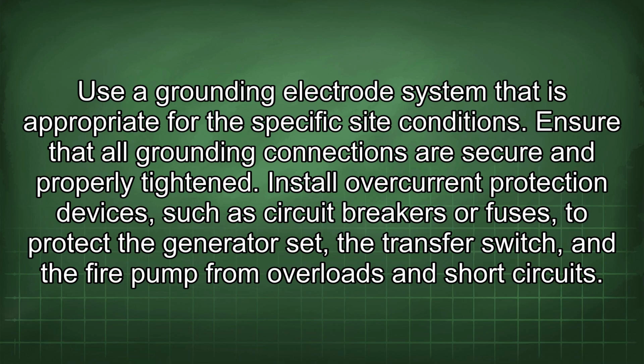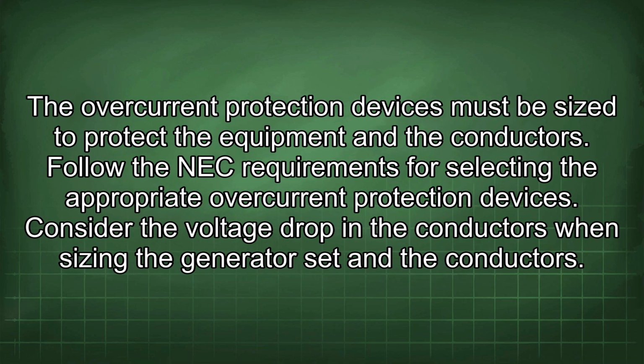Install overcurrent protection devices, such as circuit breakers or fuses, to protect the generator set, the transfer switch, and the fire pump from overloads and short circuits. The overcurrent protection devices must be sized to protect the equipment and the conductors. Follow the NEC requirements for selecting the appropriate overcurrent protection devices.